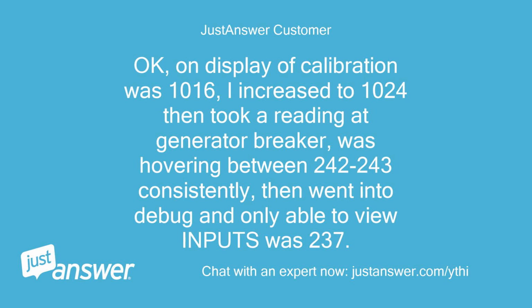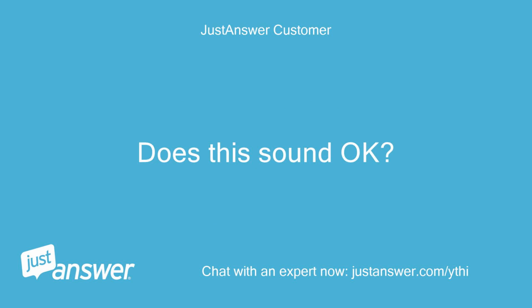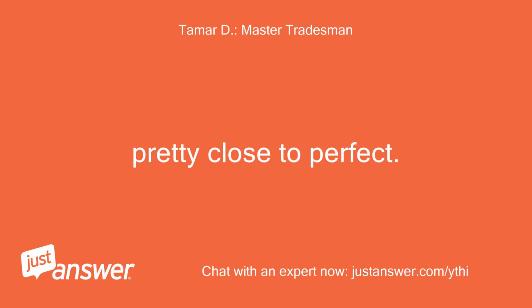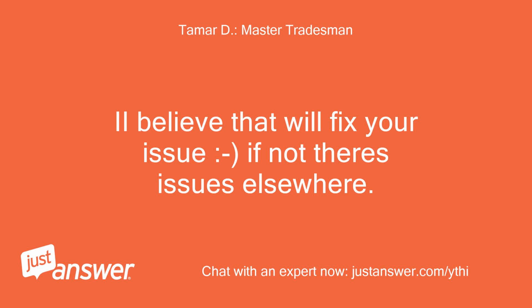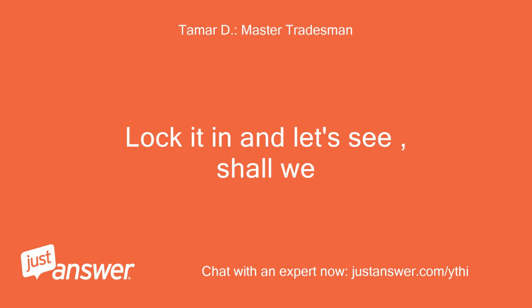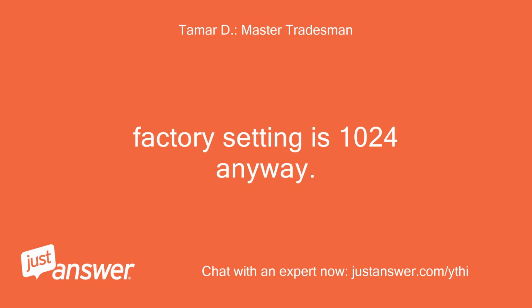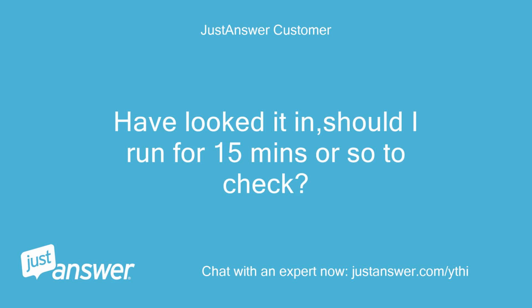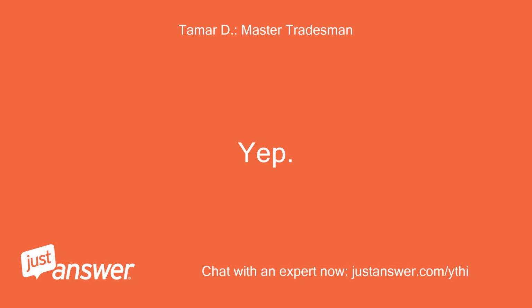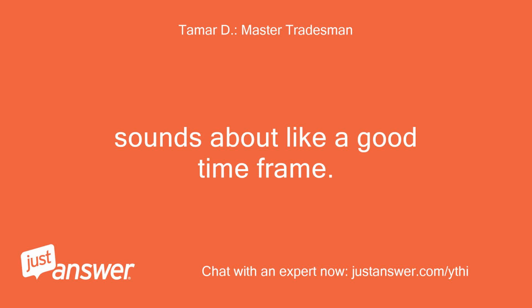Okay, on the display the calibration was 1016, I increased it to 1024, then took a reading at the generator breaker, which was hovering between 242 to 243 consistently, then went into debug and only able to view inputs, it was 237. Does this sound okay? Pretty close to perfect. I believe that will fix your issue. If not, there are issues elsewhere. Lock it in and let's see, shall we? Factory setting is 1024 anyway. I have locked it in. Should I run it for 15 minutes or so to check? Yep. Sounds about like a good time frame.